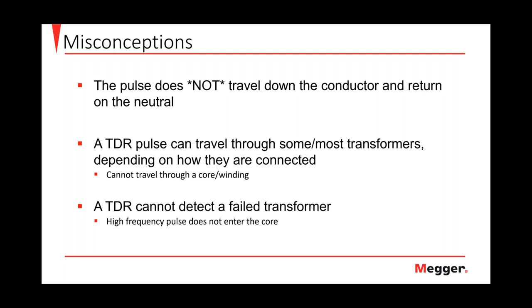They don't need to be isolated to perform TDR testing. The pulse won't travel through the core due to inductive reactance. Another one, some people think that TDR can be used as a troubleshooting tool to find faulted transformers, and it's really not designed for that. It doesn't work for that application.